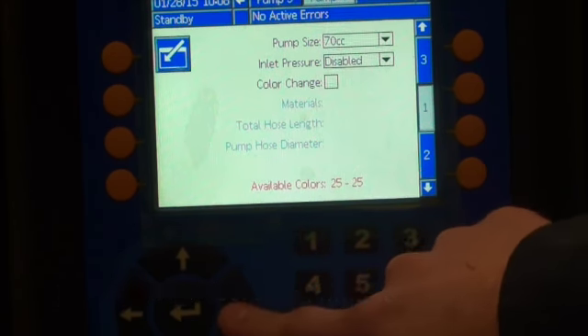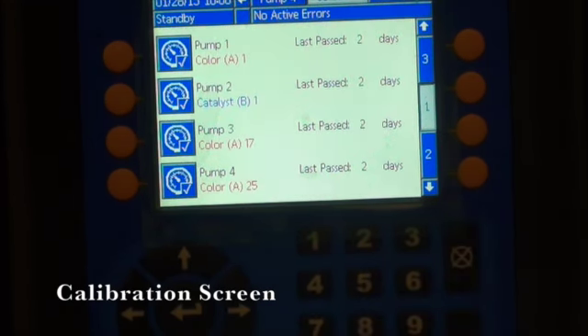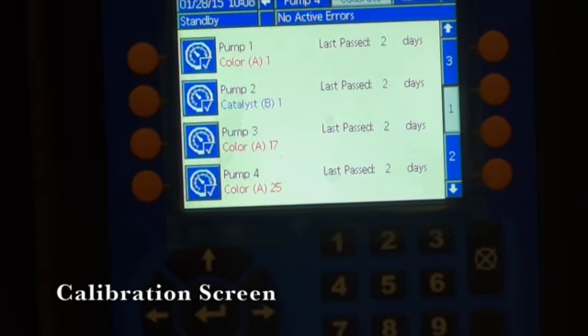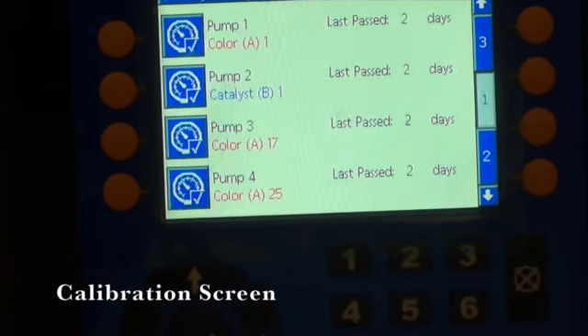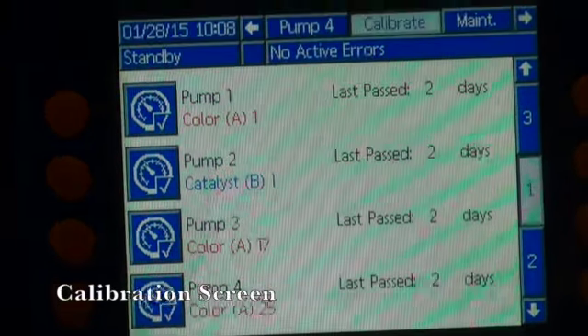The next screen is very important. This is your calibration screen. Your calibration screen is what's going to do your stall tests on each pump. The stall test is the pump is going to go on an upstroke and a downstroke, and what it's going to do is make sure that there are no leaks and it holds pressure.